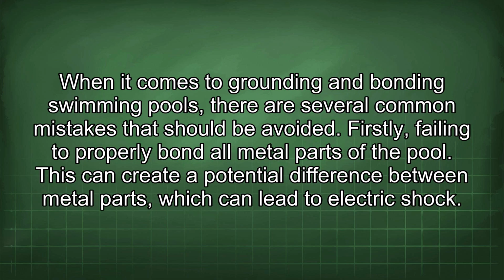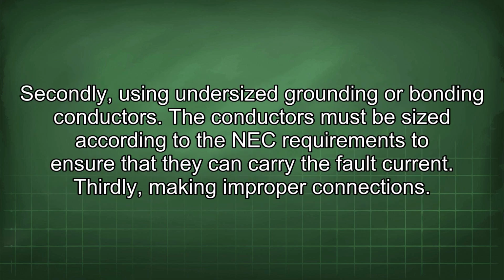When it comes to grounding and bonding swimming pools, there are several common mistakes that should be avoided. Firstly, failing to properly bond all metal parts of the pool. This can create a potential difference between metal parts, which can lead to electric shock. Secondly, using undersized grounding or bonding conductors. The conductors must be sized according to the NEC requirements to ensure that they can carry the fault current.